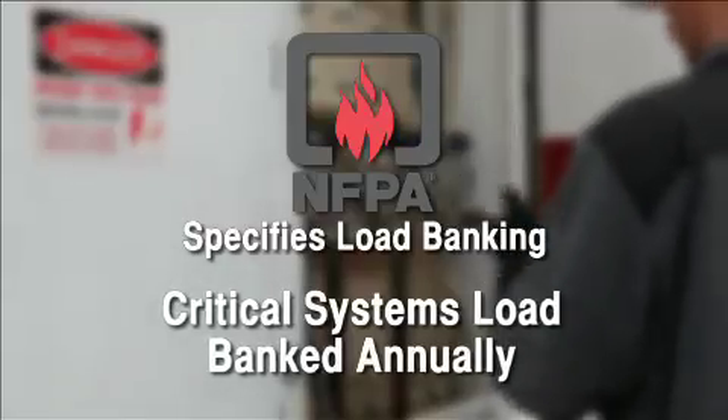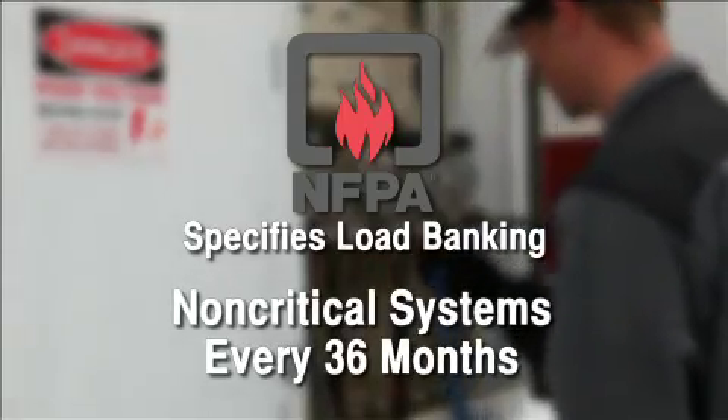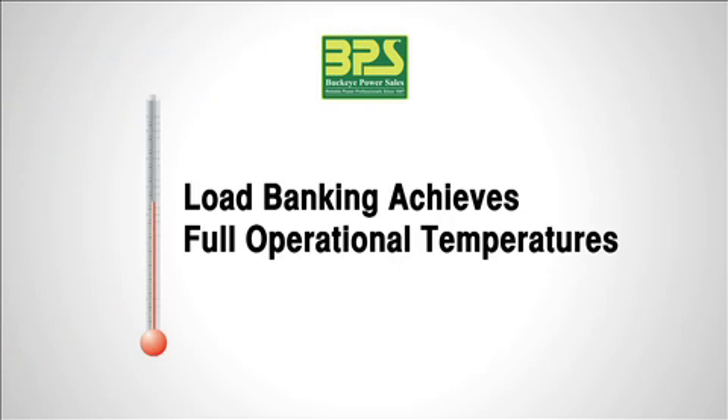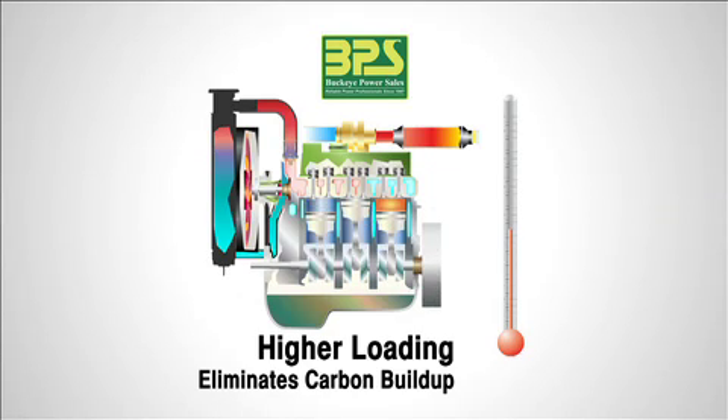The National Fire Protection Association recommends annual load bank testing of critical load generator set installations. For non-critical systems, NFPA 110 recommends load banking every 36 months. Bringing the engine to operating temperature for a period, as defined by NFPA 110, eliminates the build-up of carbon deposits and burns off unused fuel and carbon deposits in the exhaust system, a condition known as wet stacking.